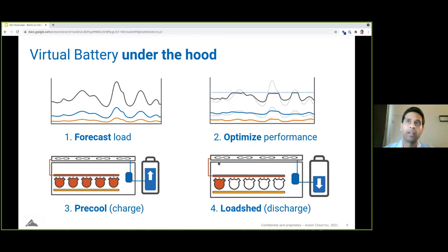Then, when necessary, virtual battery will load shed—essentially discharging the battery according to that optimized profile. It'll deliberately shut down more compressors than would have been running at that time, significantly reducing the overall building load when most favorable to do so.